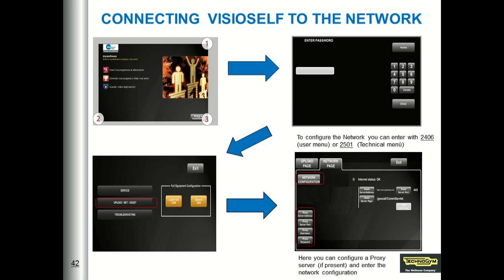In this presentation we are seeing how to connect VisioSelf to the network. The first thing to do is entering into the user or technical menu. To do that, you have to press the top right corner, then the left bottom corner, and then the bottom right corner of the VisioSelf when it is in the standby page. The VisioSelf will ask you for a password. We have two passwords: one for the customer — the owner of the facility — which is 2406, and another menu accessible using the password 2501, used by our technicians and giving access to more settings.